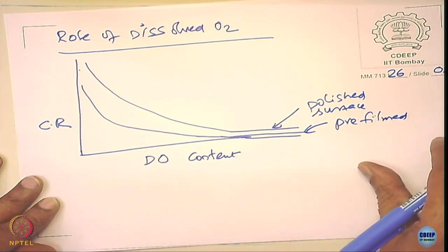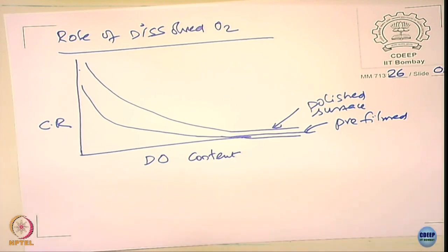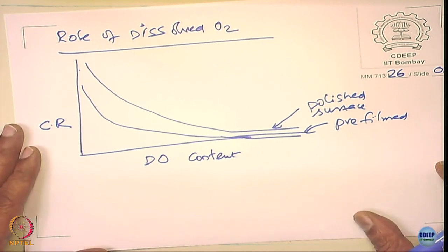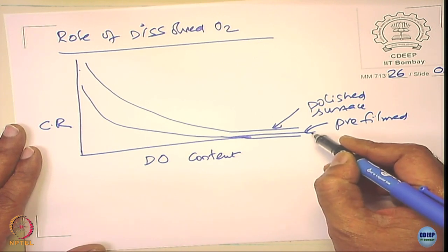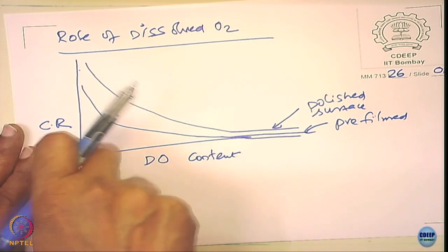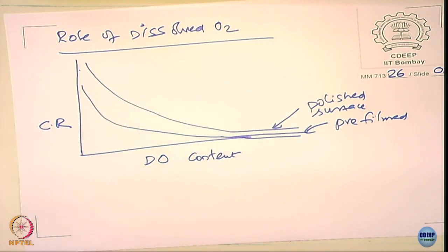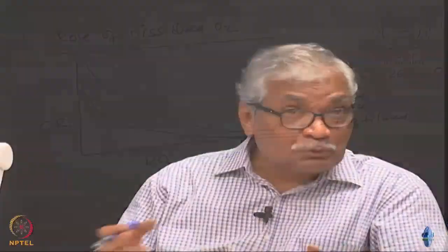Please notice that generally the boilers are passivated. This is a treatment called passivation treatment, people do, they call it alkali treatment in order to form the film. If you have a film here, it is even better. So, please notice that the oxygen content helps to decrease corrosion rate. What does oxygen do? It increases the corrosion rate, no doubt, but if it increases the corrosion rate beyond a certain level, it enriches the metallic ions on the surface and it forms a film.